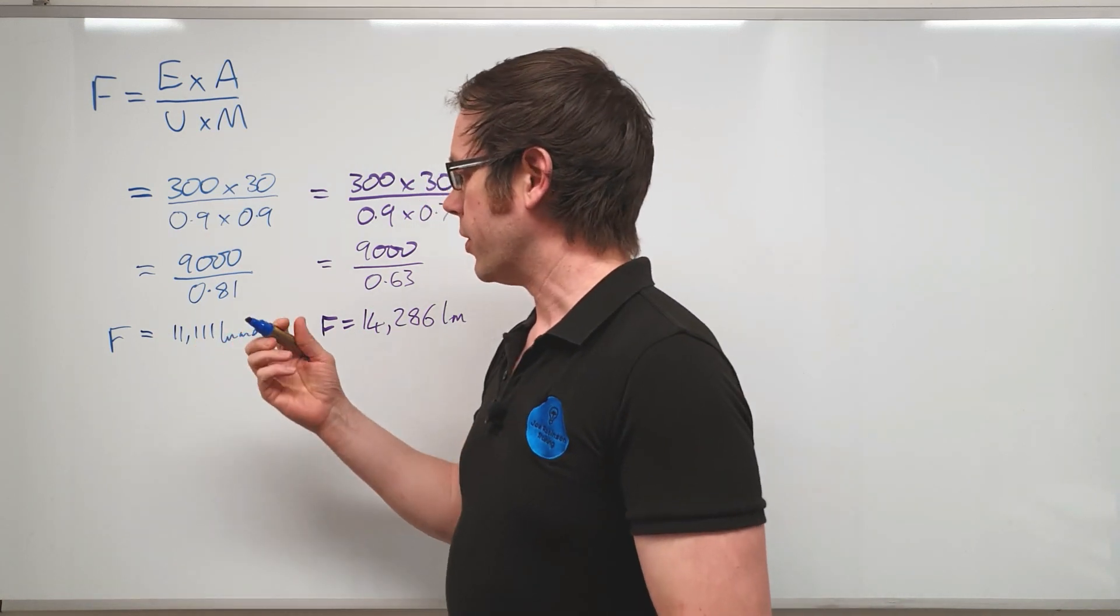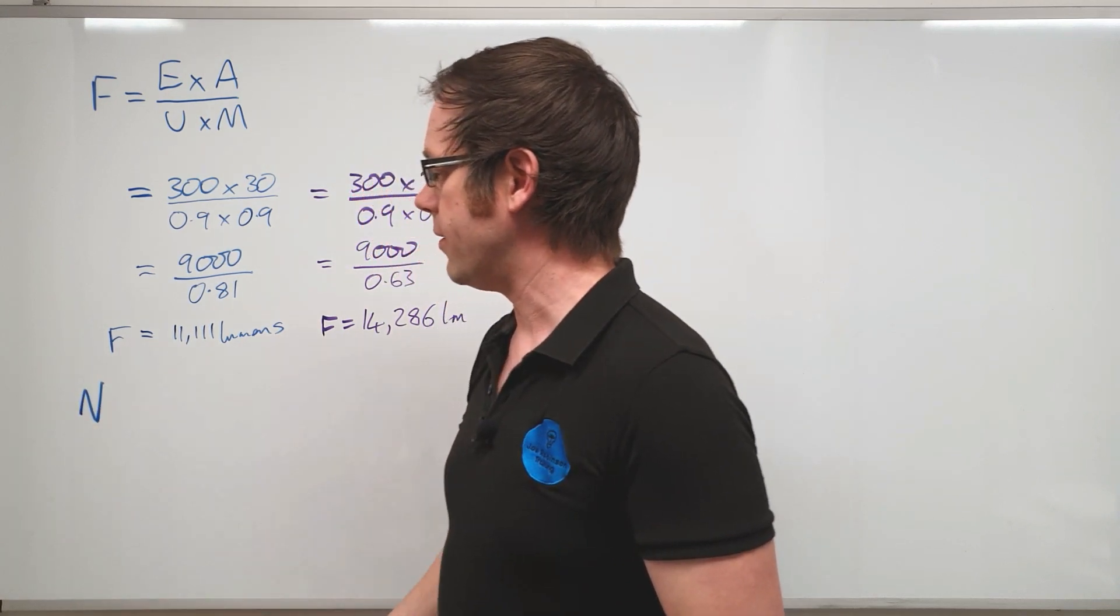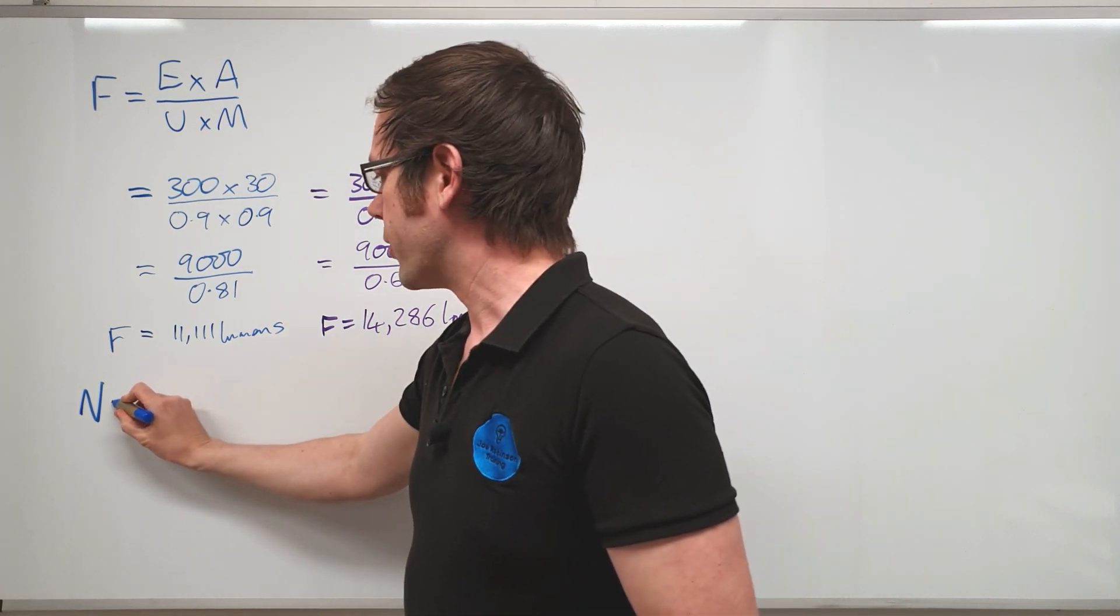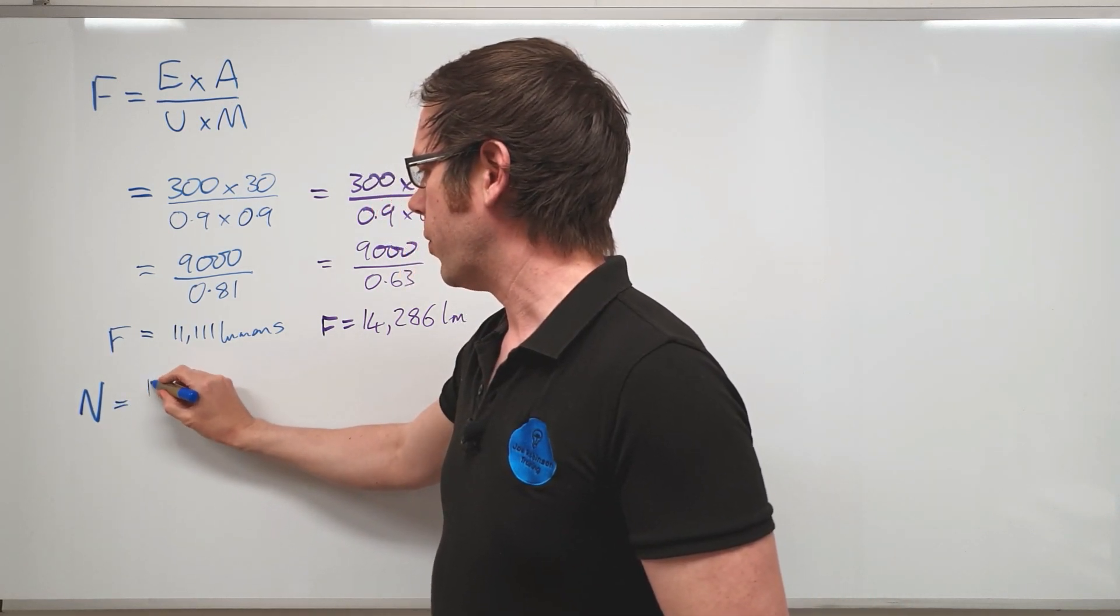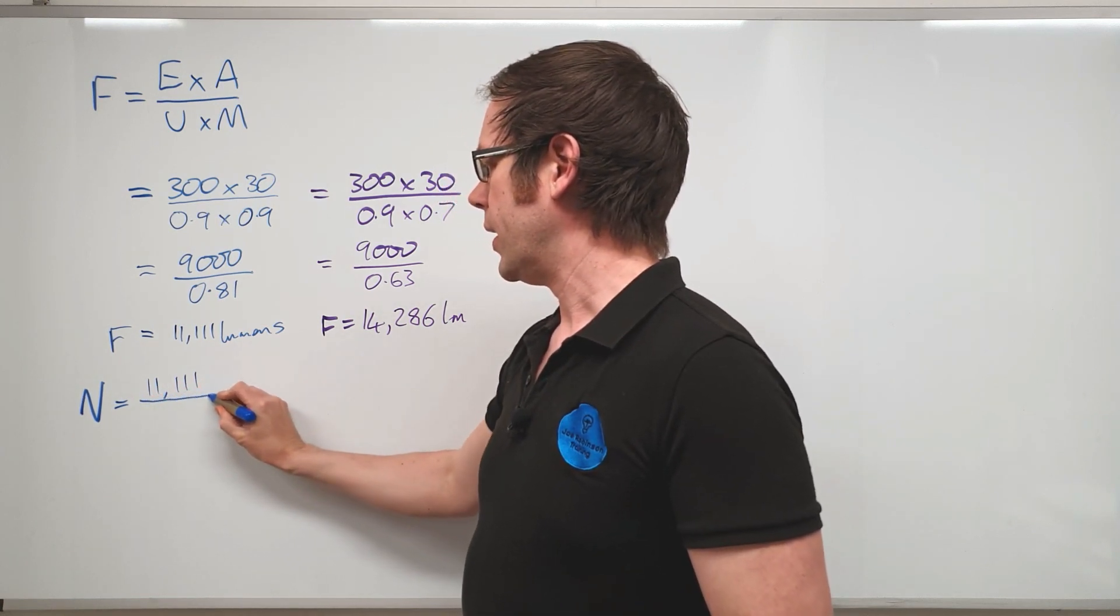All we've got to do in order to figure out the number of light fittings that we require now is to take the number of lumens required to bring the light level up to the correct value and divide it by the lumen output of the light fitting.